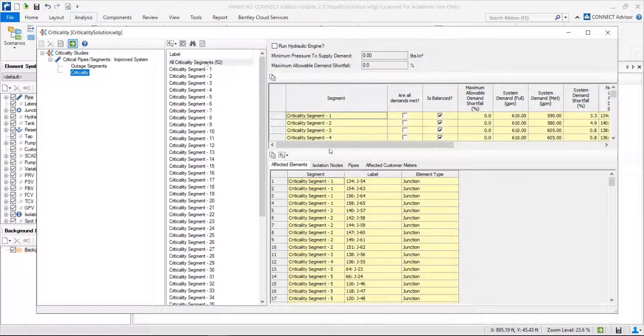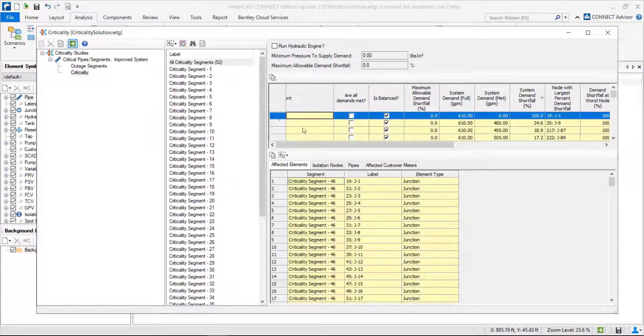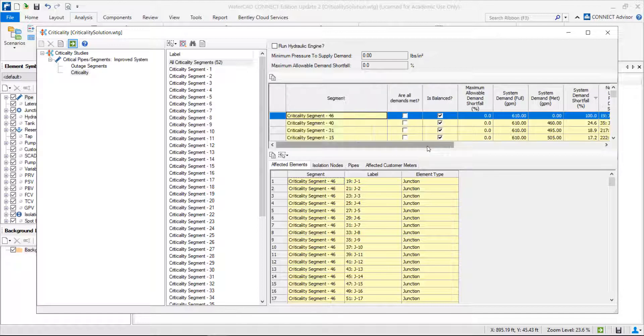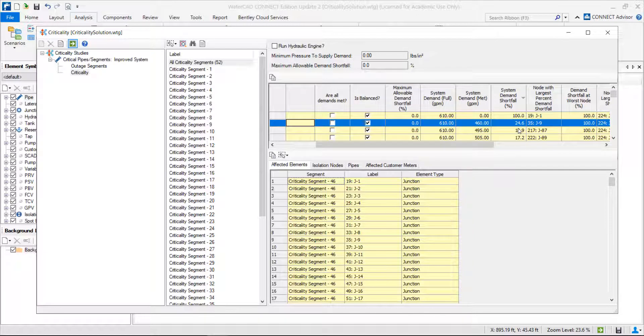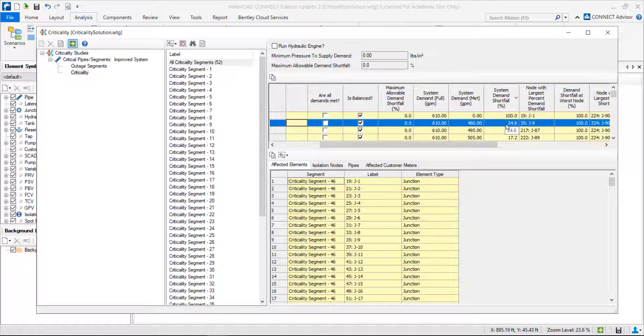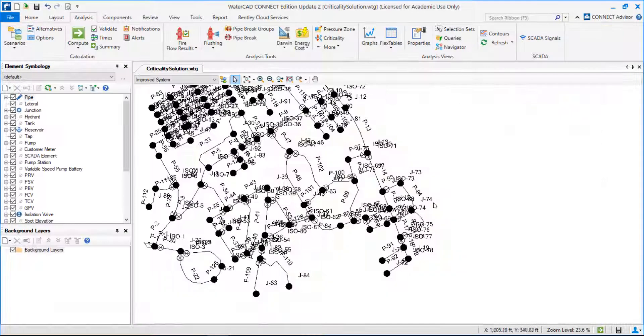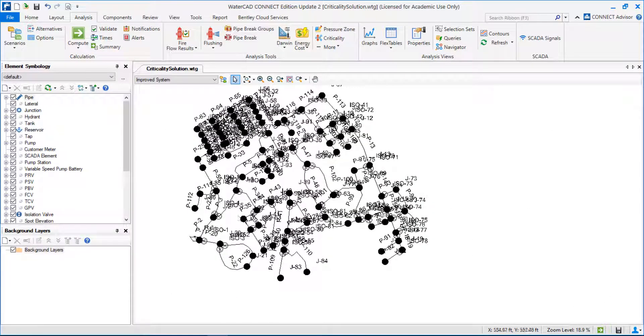The same applies for the criticality — if we look at system demand shortfall, remember we had 100% for the first critical one and almost 50% for the second one. Now the second most critical induces a system demand shortfall of only 24%. We can understand that by doing this solution, building this pipe, we are improving a lot the redundancy and decreasing the risk in our network.